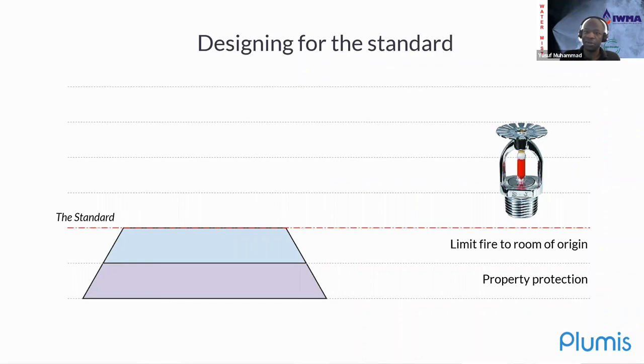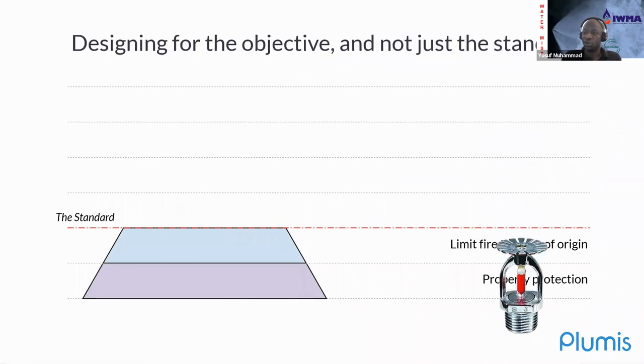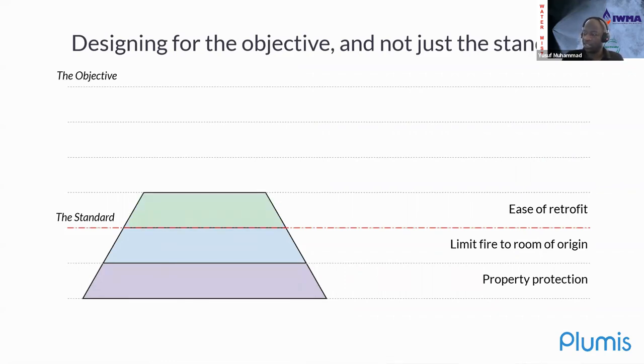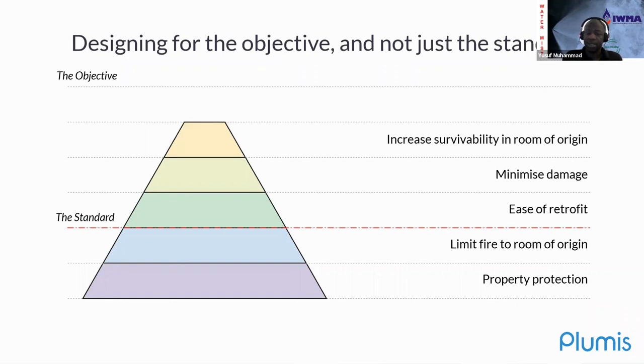Now, that's not to say that they cannot be used for life safety. Of course they can. The fire performance can also be fire engineered and applied in different ways. But I say this because this was one of the initial design objectives of traditional sprinkler systems. And what we're looking to do with Automist is elevate the system with a slightly different objective, where we meet this initial benchmark, but go further, looking to address things like ease of retrofit, so we can have greater adoption of active fire suppression systems, minimize damage, and also look to increase survivability in the room of origin through early activation and smart detection.